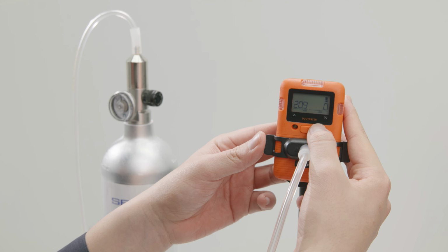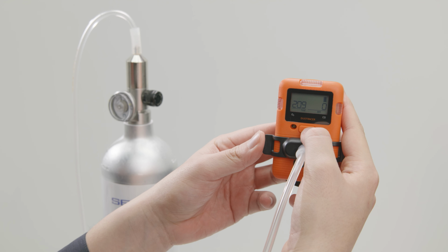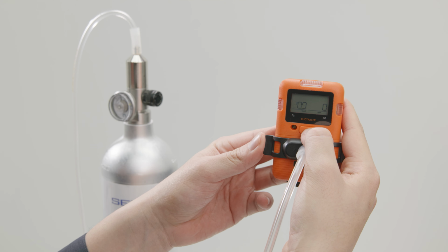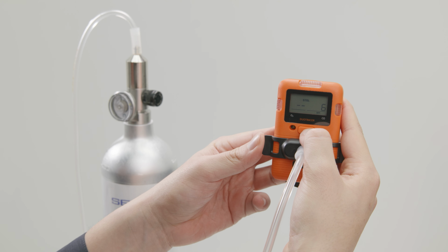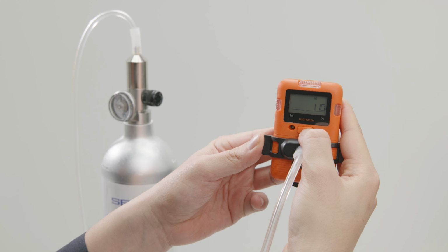Now, let's take a look at how to perform a bump test. A bump test is a quick check to make sure the sensors and alarm functions are working properly. It's important to note, this is not a test to correct measurement accuracy. It's simply a functional check to confirm that the sensor responds to gas and that the alarm is triggered as expected. The process is very similar to span calibration.